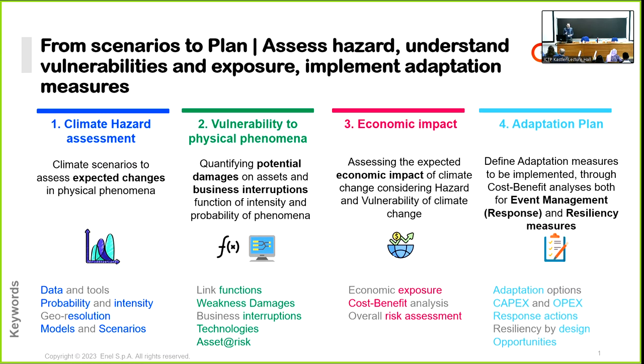It's very important for us to develop metrics that fit into our vulnerability modeling. One key opportunity is to collaborate on developing sectorial metrics, because right now we have our own metrics, but it would be very useful to have metrics shared at the sectorial level to set standards. For example, to assess the impact of heat waves on our underground cables, we correlated heat temperature, rain, and other variables with our fault data to get a definition of heat wave correlated with our faults. This leads us to the point that to deliver adaptation we need local analysis.